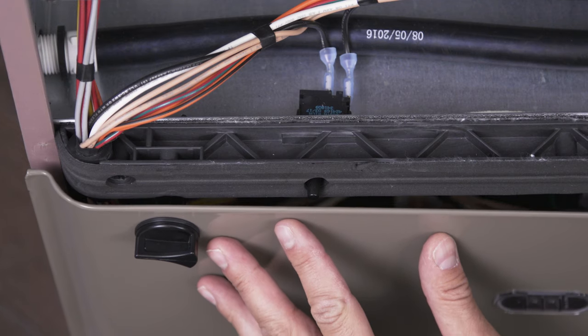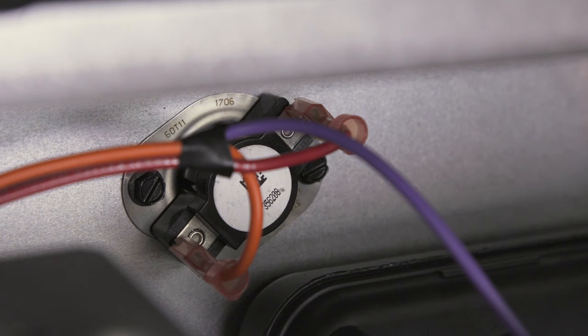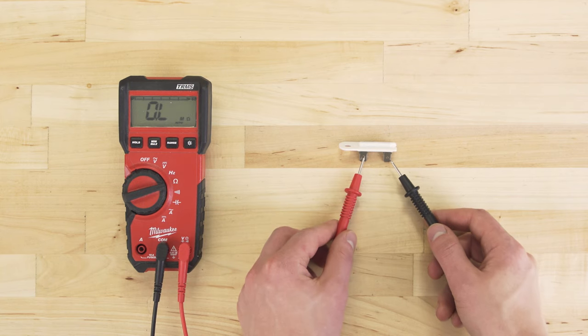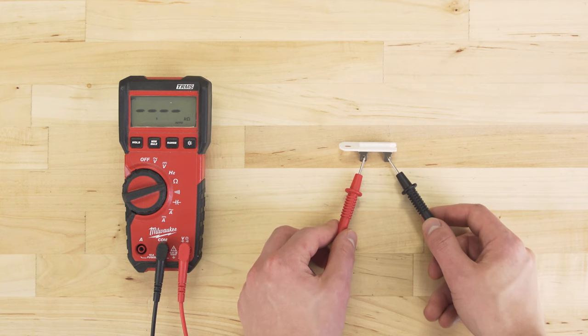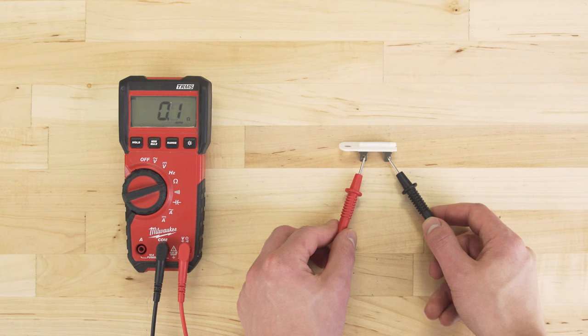Non-load components such as switches, thermostats, or fuses provide an unrestricted path for the electricity to pass through. These will typically have a resistance reading between zero and one ohm.